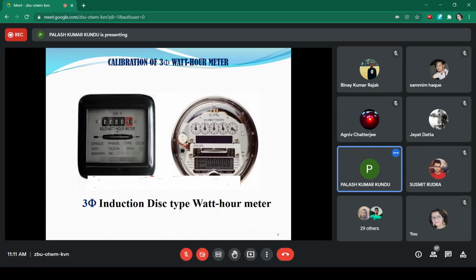The value of the meter constant may be high or low. If the value of the meter constant is very high, the sensitivity of the energy meter will definitely be high, because the meter will be able to measure the smallest variations of the kilowatt hour. If the value of the meter constant is low, the sensitivity is low, which means the meter is not able to sense small changes with the help of disc rotation.